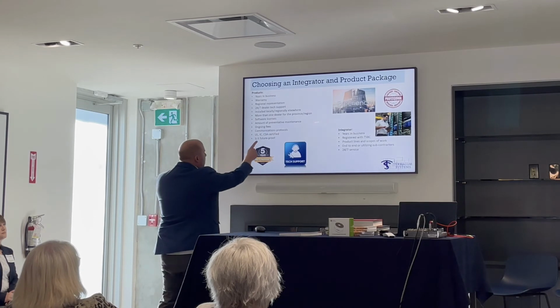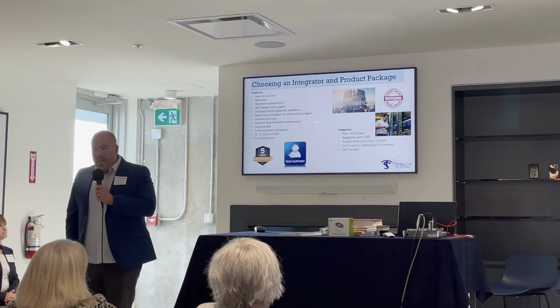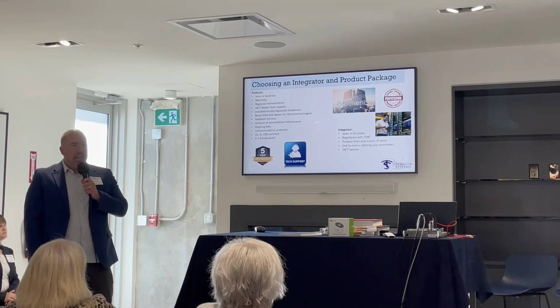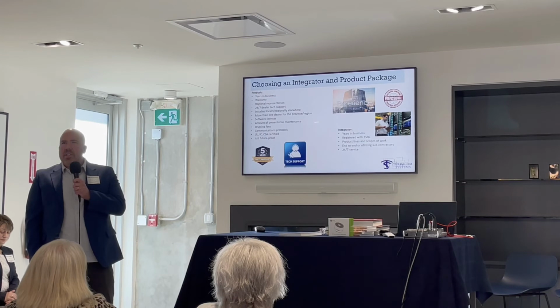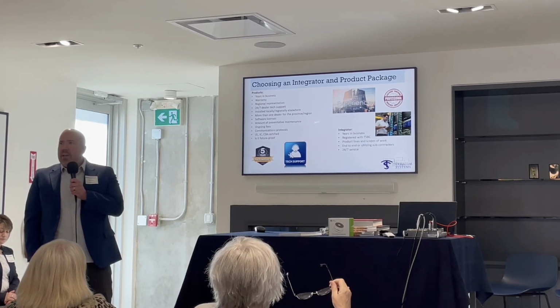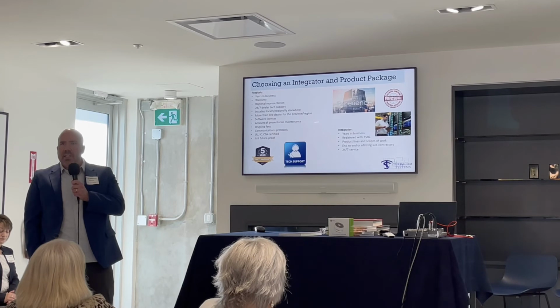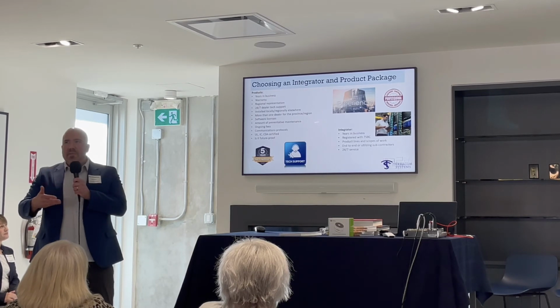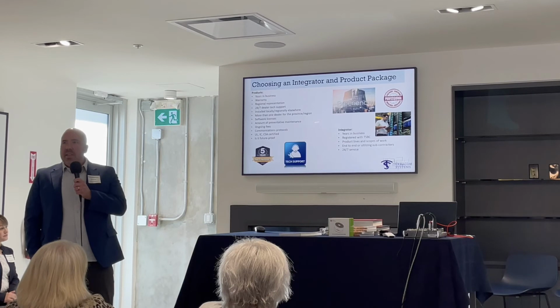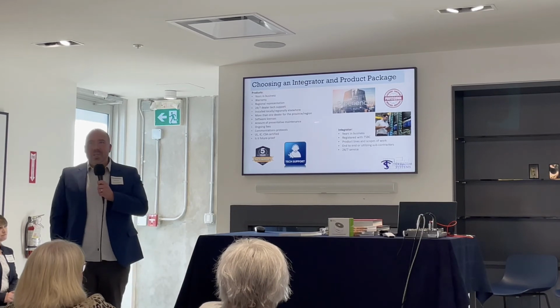Like I said about the UL, but one thing too you got to watch out for is Industry Canada and Canadian Standards Association certification. I got a call about a year ago for a site that got a code white staff arrest system put in. It was a kind of a mental health building, and the company that put it in went out of business. They had me look at it, and I started looking at the stuff I've never seen before, and I saw it didn't have any kind of Industry Canada certifications or UL certifications, so I had to take some pictures of the circuit boards and Google it, and I saw it was some stuff out of Israel that this company had just bought straight from Israel and installed at this site up in Kelowna, and it was on a frequency band that wasn't even legal in Canada. So yeah, you got to be careful that you're getting stuff that is certified to be used in Canada.